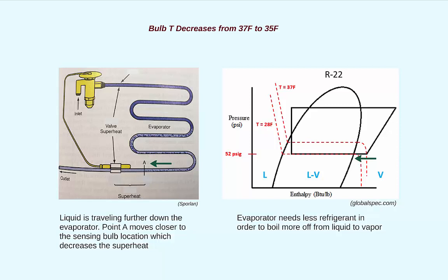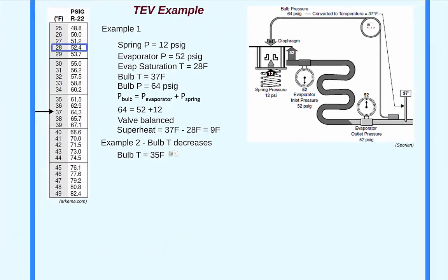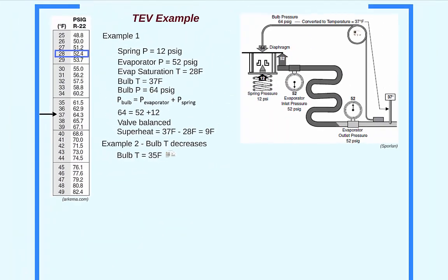are approaching the saturation region on the pressure enthalpy diagram. This is actually a sign that we have too much refrigerant in the evaporator. In order to restore the desired superheat, the flow rate to the evaporator needs to decrease. With less refrigerant in the evaporator, more of the heat extracted from the indoors will be available to increase the refrigerant temperature back to 37 degrees. Since the bulb temperature decreased, we should expect to see the expansion valve respond by closing in order to decrease refrigerant flow. Let's see if that's what happens.